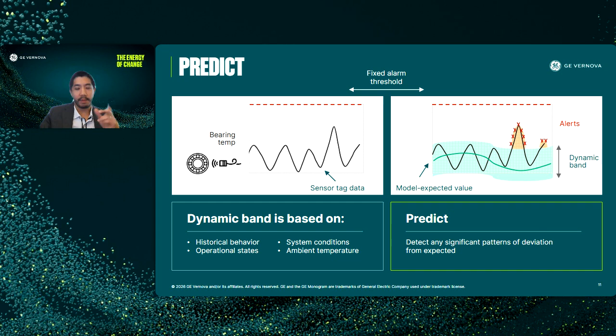The system can detect this deviation in what we call a residual—that's the green envelope you see, the difference between the actual sensor data and the predicted value. Because the model knows what the asset should be doing during that specific load and condition, it can flag issues weeks before it ever reaches that red dotted fixed alarm. So detection is one thing, but to be effective, we need to know the why, and we need that detection to be even more concrete.